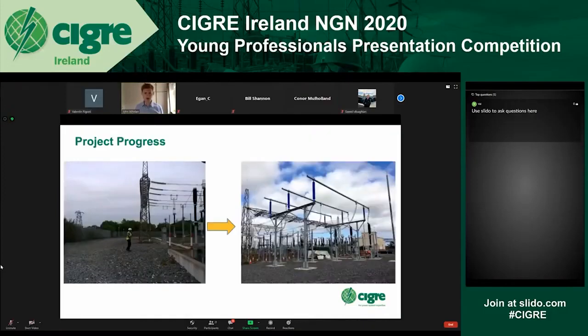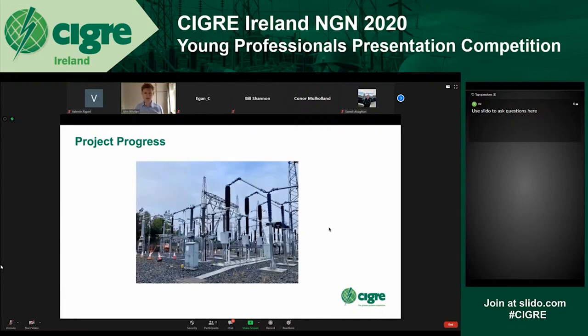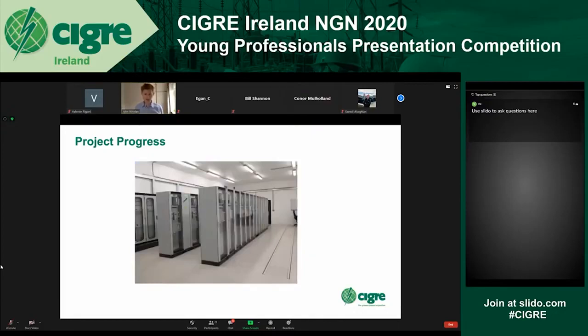Project progress: both ring coupler bays have been fully built and commissioned. The new cable bay for Belcamp station is fully built and commissioned. The new control room to house the new scheme is commissioned - each bay has a dedicated cabinet and a GRB bay unit. The bay units take in their measurements from the bay outside and feed this information to the GRB central unit. The central unit then, based on the measurements it's receiving, uses differential protection to determine any protection decisions it needs to make in the station based on the varying zones and how it is set up.